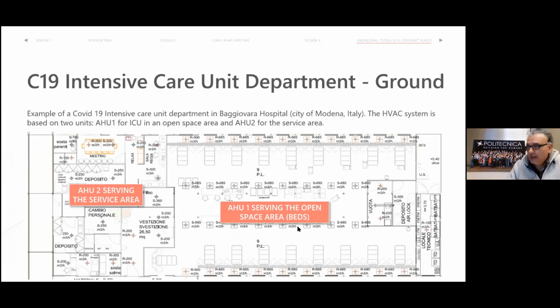Inside here, this is a plan, more or less. We have already seen even some 3D drawings. As you see here, there is a supply. So the supply is concentrated in the middle of the room. This is the intensive care area. And the return, so the extraction, is concentrated near the beds of the patients, so that we have more or less a clean area in the middle. So clean area maybe is too much, but however, a less risky area in the middle. While if you approach the patient, when you are close to the patient, this is a more risky area because of contamination. And over there is extraction immediately.